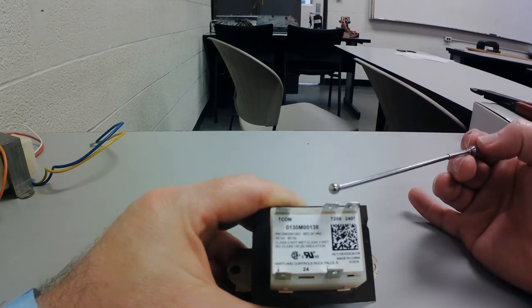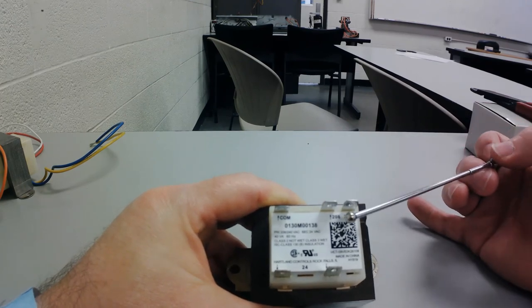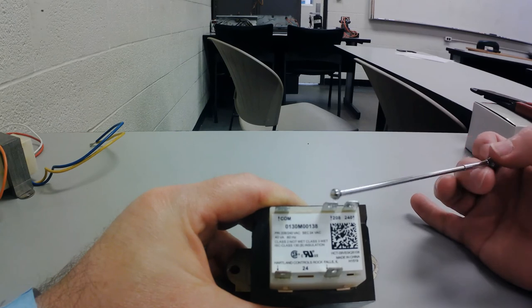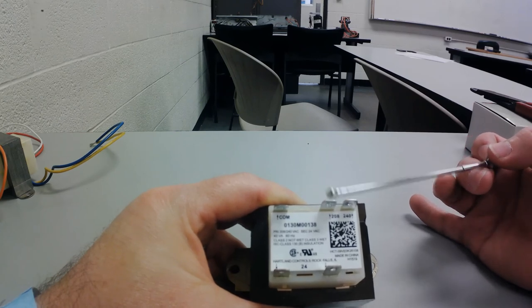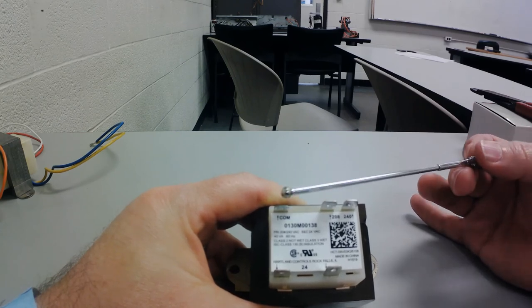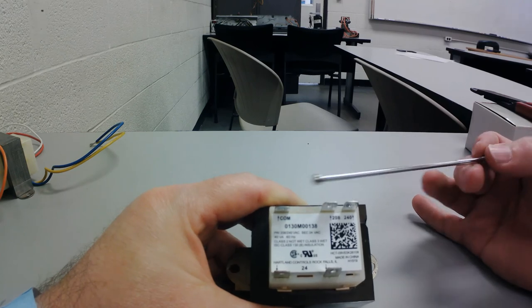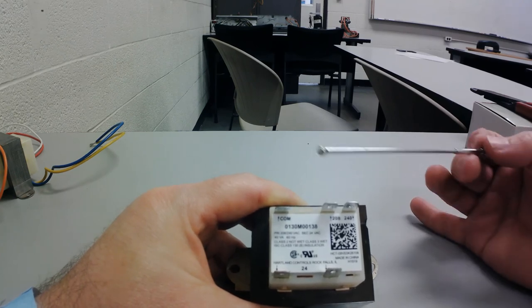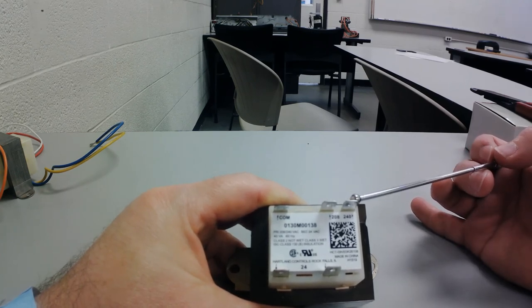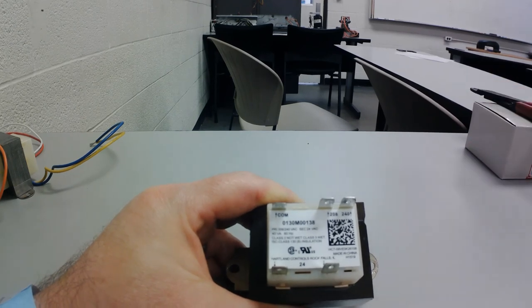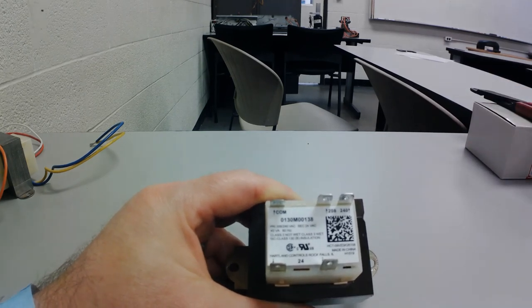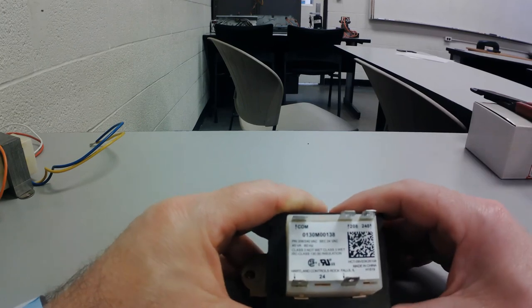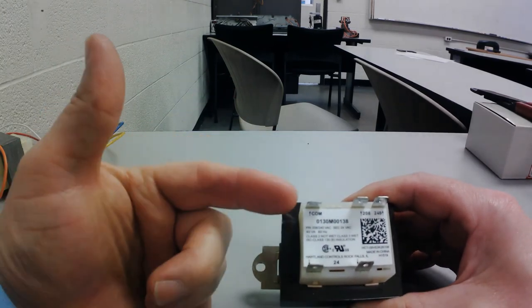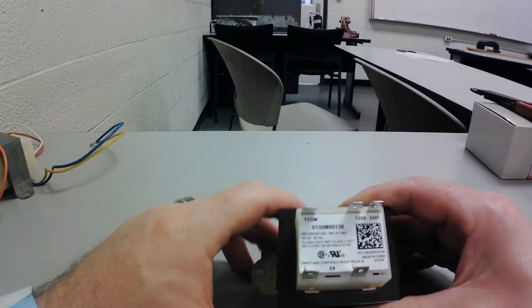So make sure that if you're going to use the 208 and common, you put 208 volts. Don't put 240, put the 208. If your power source is the 240, then you make sure you use 240 and common. Don't use the 208, okay? Make sure that you properly supply power to the transformer, and when you do that on the input side, you'll get what you need on the output side.